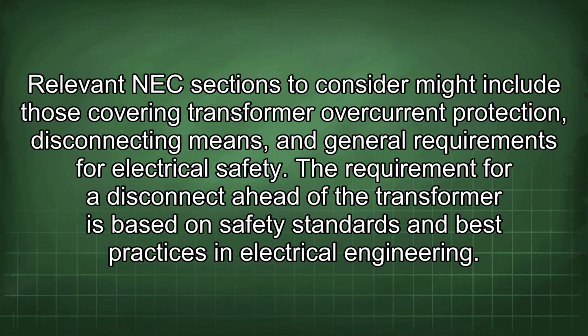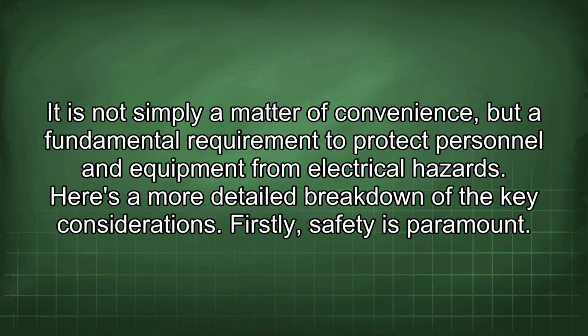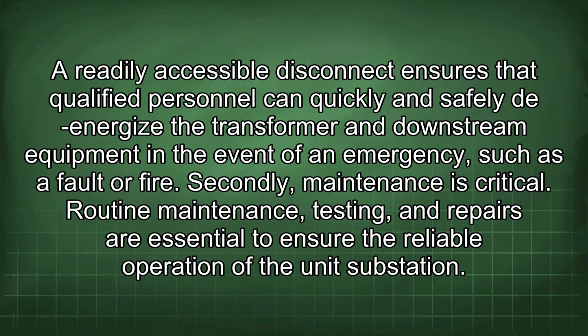The requirement for a disconnect ahead of the transformer is based on safety standards and best practices in electrical engineering. It is not simply a matter of convenience, but a fundamental requirement to protect personnel and equipment from electrical hazards. Here's a more detailed breakdown of the key considerations. Firstly, safety is paramount. A readily accessible disconnect ensures that qualified personnel can quickly and safely de-energize the transformer and downstream equipment in the event of an emergency, such as a fault or fire.